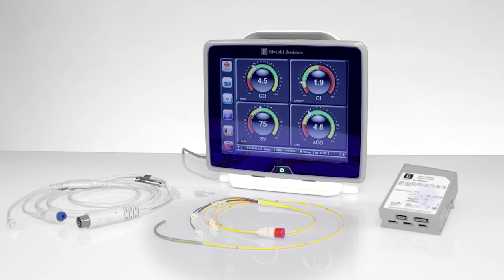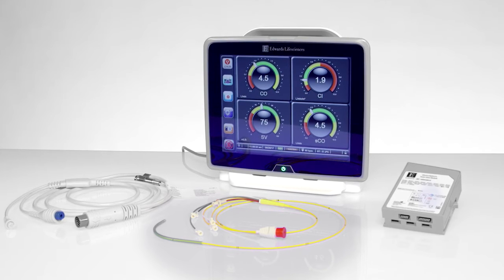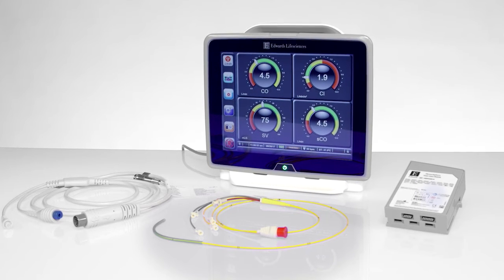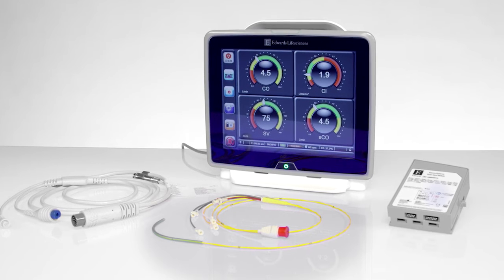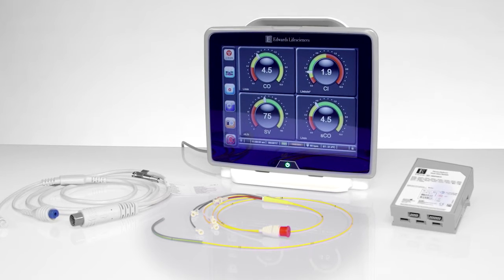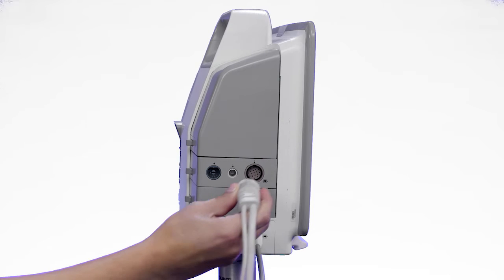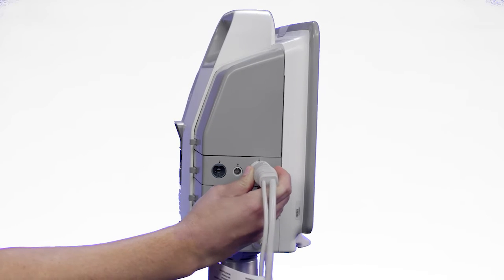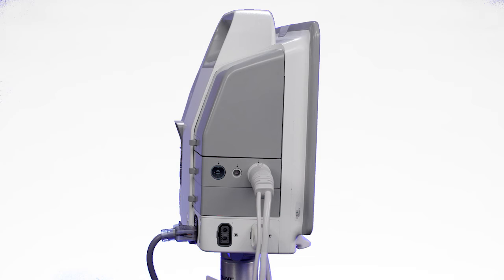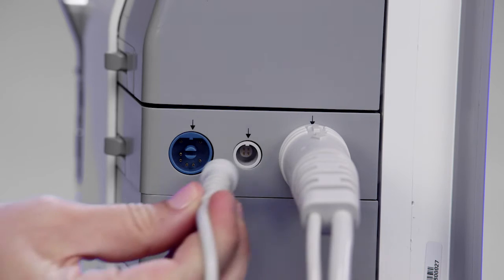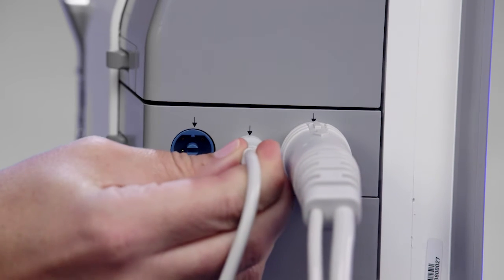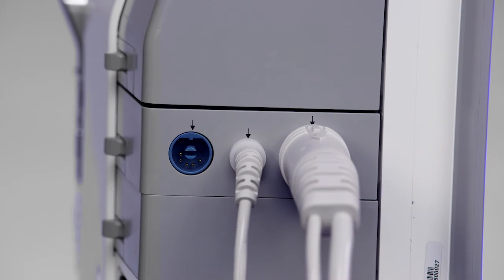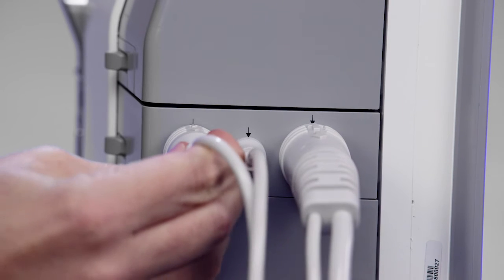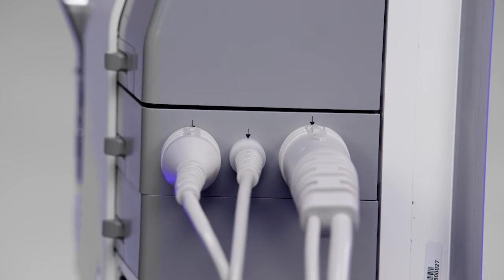Before connecting the catheter to the patient CCO cable, connect the patient CCO cable to the HemoSphere Swan-Ganz module of the HemoSphere Advanced Monitor. Do this by first inserting the gray connector of the CCO cable into the gray port on the HemoSphere Swan-Ganz module. Second, insert the thermistor connector into the middle port. And finally, insert the thermal filament connection into the blue port.